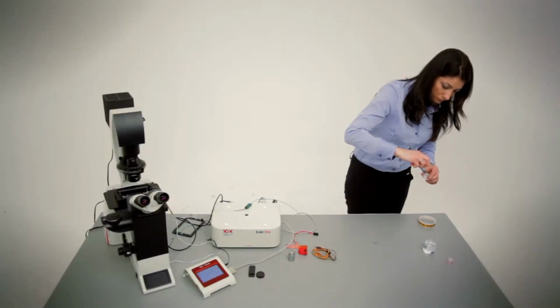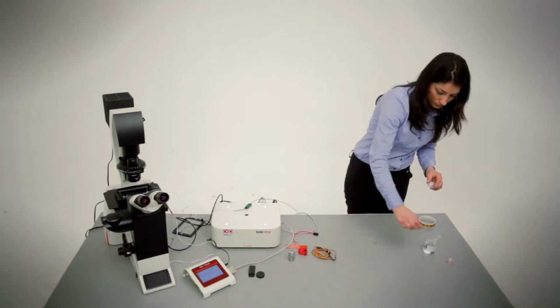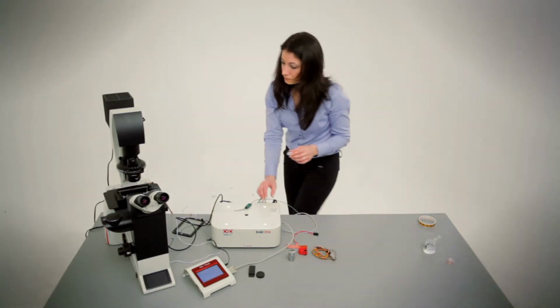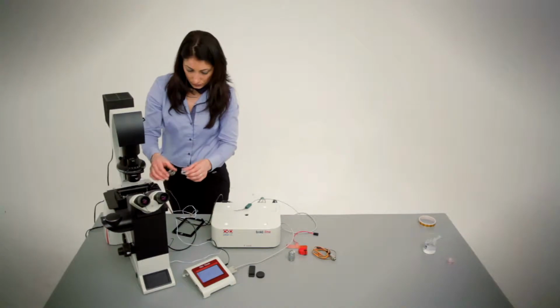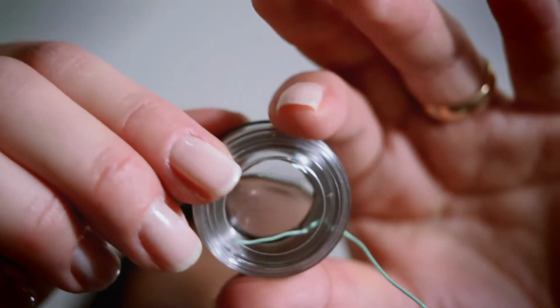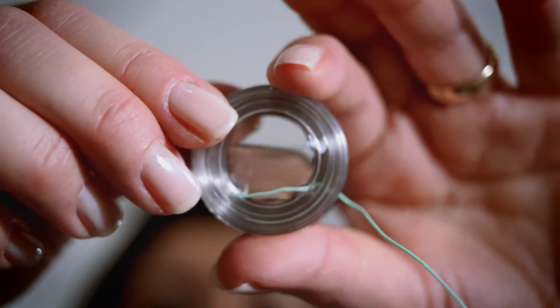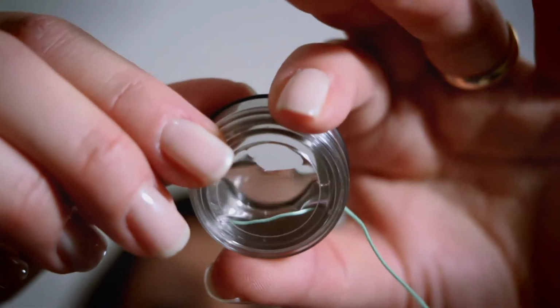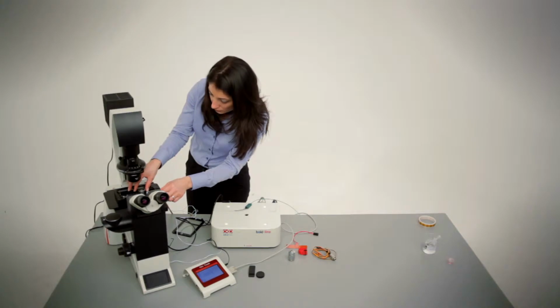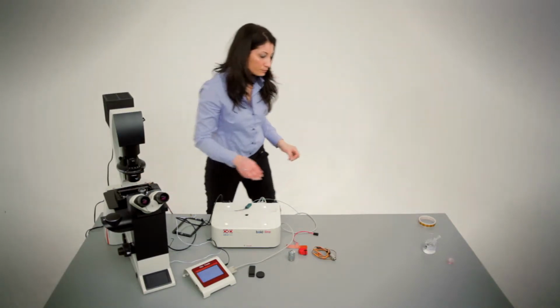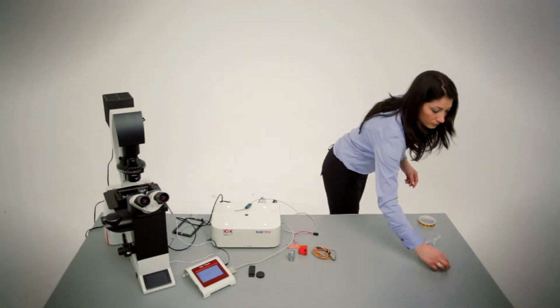Introduce 3 milliliters of distilled water in a 35 millimeter Petri dish and cover it with the sensor lid. Make sure that the sensor is touching the bottom of the Petri and is covered with water. Position the Petri with the sensor lid inside the chamber, next to the sample.